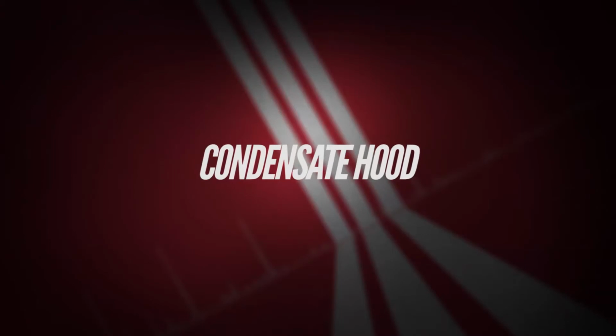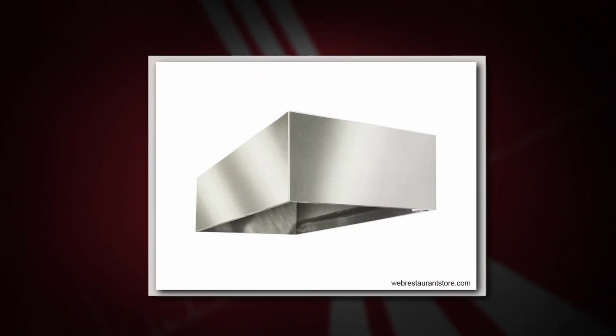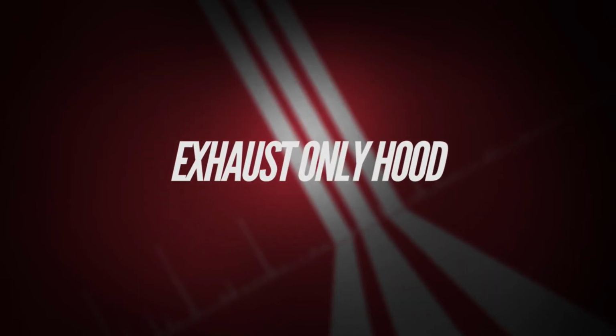Let's now go over some of the typical styles of hoods that you would see in different restaurant applications. These images will help you visualize what I'm talking about. First, condensate hood. Condensate hoods, as Bill mentioned, are used for the extraction of steam and heat, mainly from commercial dish machines. Exhaust-only hoods are used for light-duty applications to exhaust heat and contaminated air from a cooking appliance, typically an electrical appliance such as a half-size convection oven, something of that sort. Next, your canopy hood.